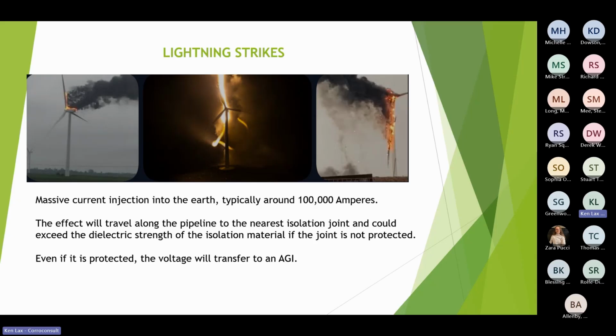But you can expect around about 100,000 amps from a single strike, and it will affect the pipeline and it will travel to the nearest isolation joint. And if it exceeds the dielectric strength of the isolation joint, the joint will fail. But even if the protection device kicks in and it bypasses the insulation material, so it doesn't affect the dielectric properties of the insulating material, that voltage will be transferred into the AGI or the compressor station or the pump station. So it increases the risk to people who happen to be working there at the time.